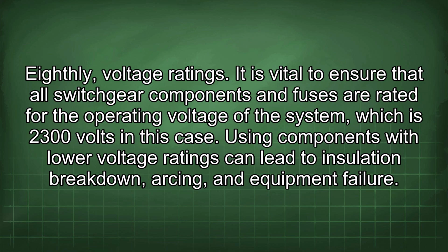Eighthly, voltage ratings. It is vital to ensure that all switchgear components and fuses are rated for the operating voltage of the system, which is 2300 volts in this case. Using components with lower voltage ratings can lead to insulation breakdown, arcing, and equipment failure.